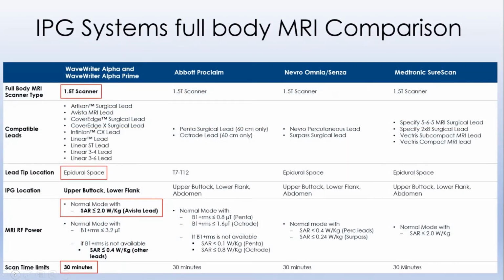So let's have a look at what it looks like between the various producers of SCS devices. All of those, as you see here, have 1.5 T scanners, so there is no 3 Tesla scanner yet. For the leads, you can see that the WaveWriter Alpha can include all types of leads and is superior to the other companies. Lead tip location, well, they're all in the epidural space. As you can see, for Abbott there is a restriction that the tip has to be T7 to T12, which I think is a disadvantage. IPG location can be upper buttock, lower flank, or the abdomen. So there are three different ways we can put it.